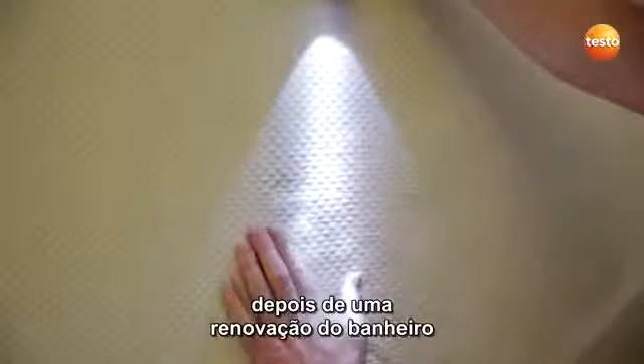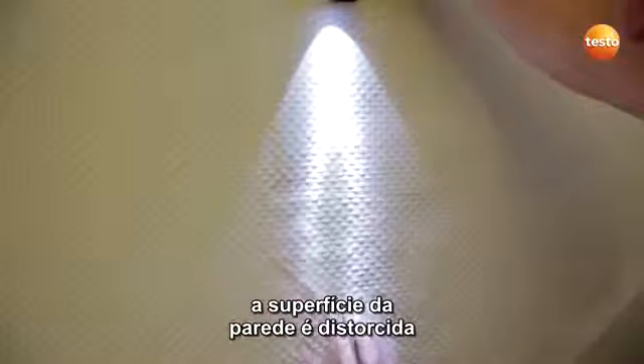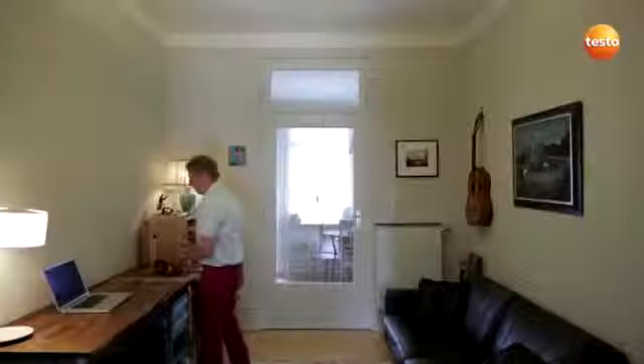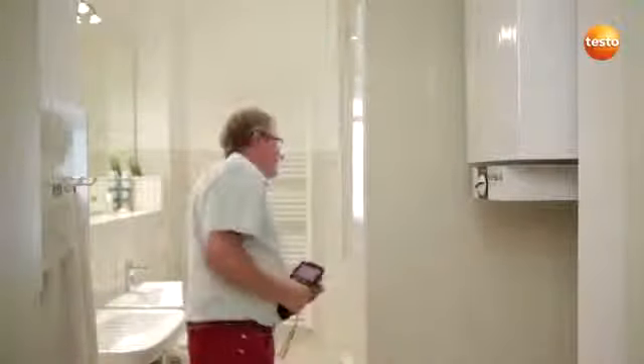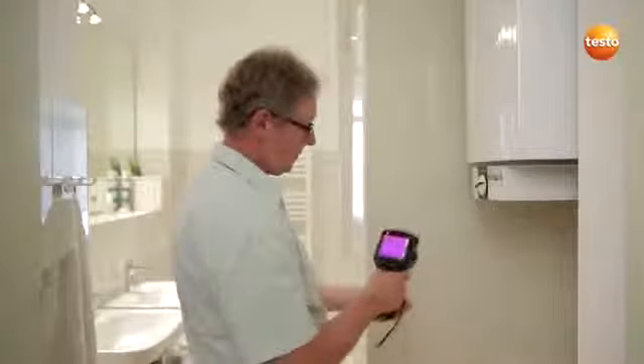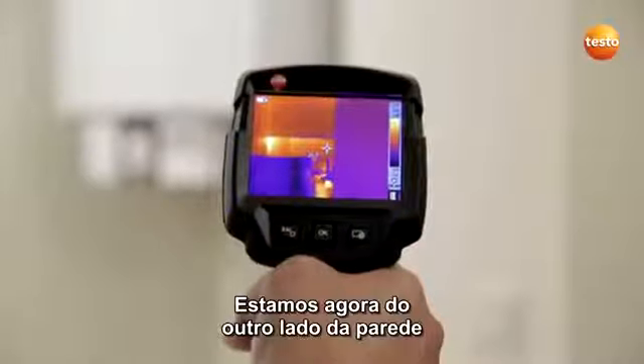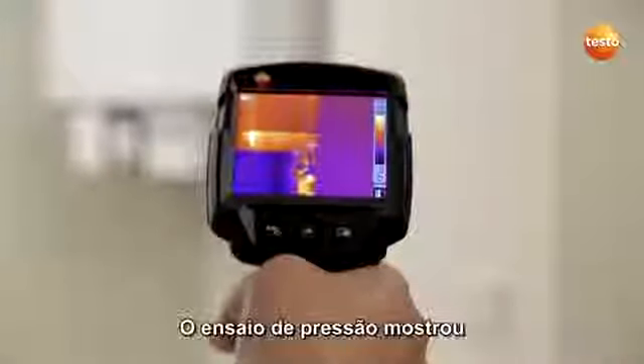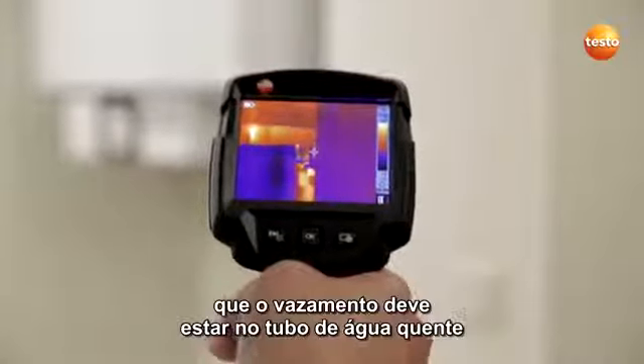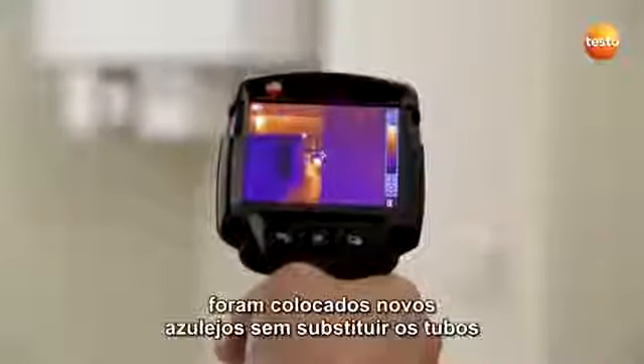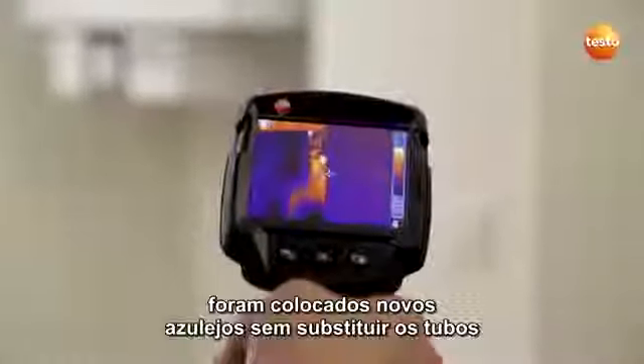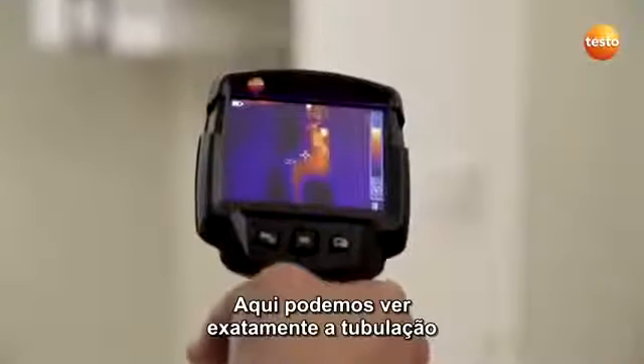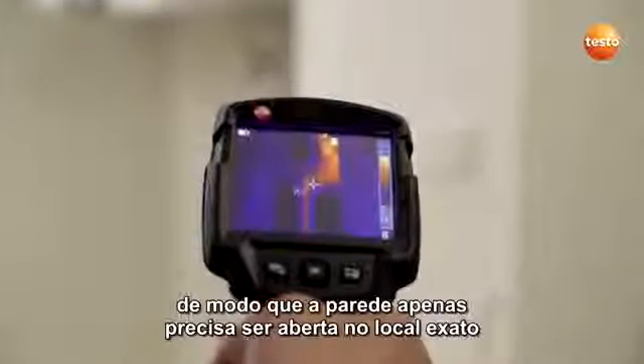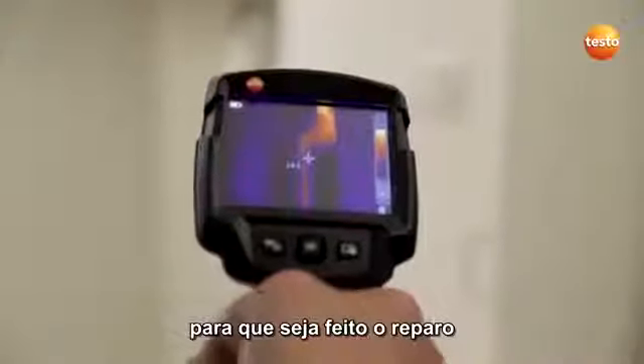A damp spot has developed after renovation of the bathroom. The surface of the wall is distorted. We're now on the other side of the wall. The pressure test has shown that the leak must be in the hot water pipe. During the renovation, the bathroom was re-tiled without replacing the pipes. Here we can see exactly where the pipe runs, so the wall only needs to be opened where the pipe is in order to carry out the repair.